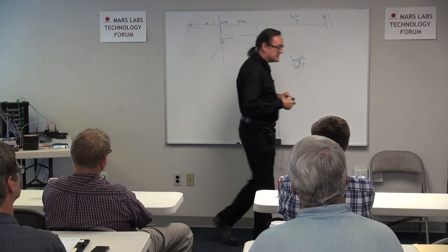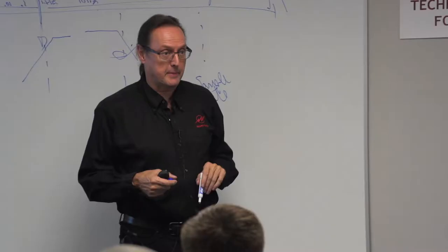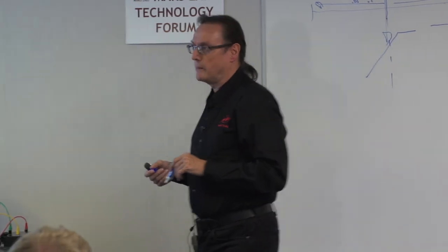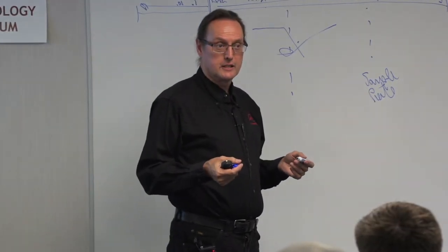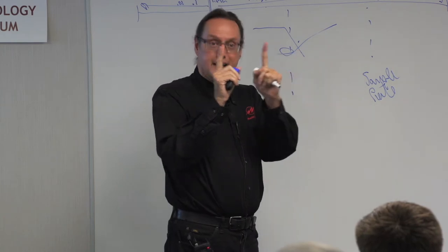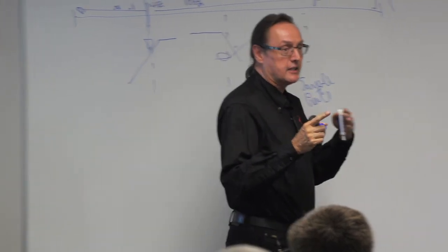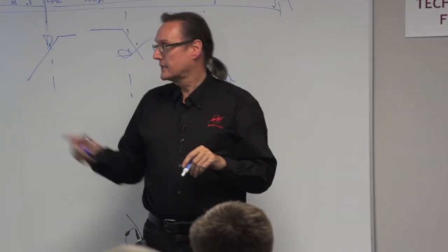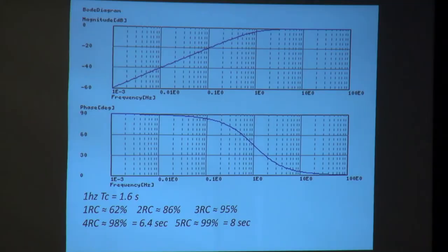Mike called many years ago — he had a PCB quartz accelerometer going into a BMK amp at 0.1 or 0.2 Hz. A common scenario: quartz-based accelerometer on a brake test, you drive through a water puddle, water gets on it. You get an instant temperature change that physically condenses or expands the housing that your shear-based crystals are in, causing all kinds of effects. Things need to stabilize back out, and that time constant starts to matter. I'd say 1 Hz is the setting, tunable below, but I wouldn't go below 0.1 Hz.